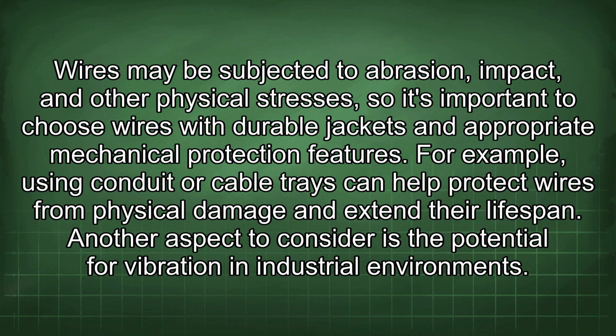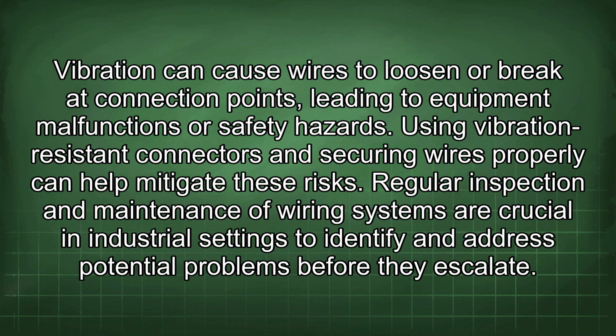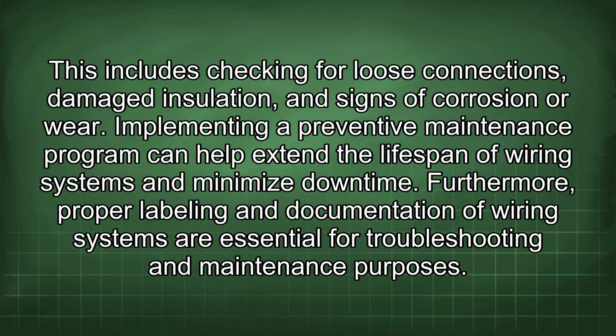Another aspect to consider is the potential for vibration in industrial environments. Vibration can cause wires to loosen or break at connection points, leading to equipment malfunctions or safety hazards. Using vibration-resistant connectors and securing wires properly can help mitigate these risks. Regular inspection and maintenance of wiring systems are crucial in industrial settings to identify and address potential problems before they escalate. This includes checking for loose connections, damaged insulation, and signs of corrosion or wear. Implementing a preventive maintenance program can help extend the lifespan of wiring systems and minimize downtime.